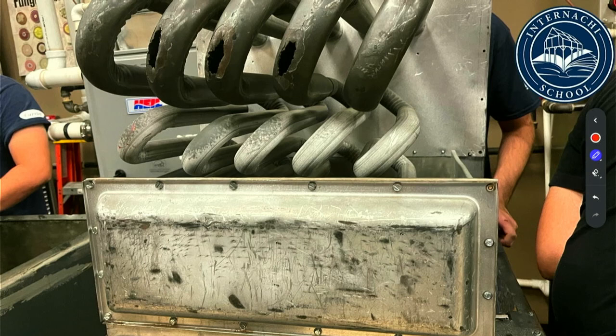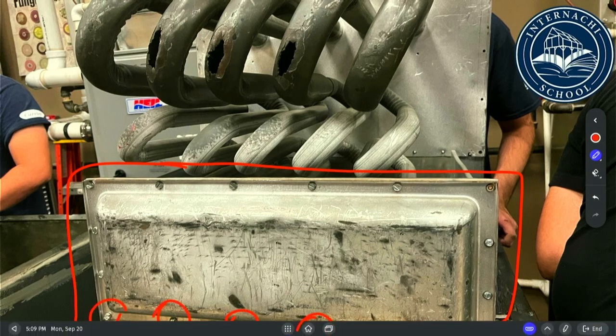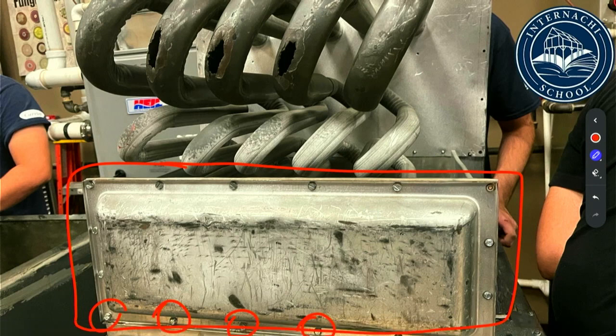This one here, they just had too much oxygen coming in. Now if we ever see stuff like this plate, I'll show another picture in a bit, something we are able to see when doing an inspection is rust at these screw holes in the bottom. If these are rusted at all, then we got a problem. That means our whole secondary heat exchanger is starting to rust out as well.